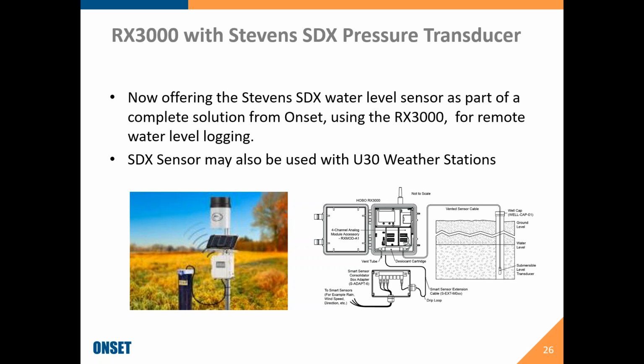The great thing about the RX3000, which is an update to the preceding U30 remote series, is that instead of having to configure an analog module at the beginning of your order and being stuck with it, unable to remove or add another one later, the RX3000 gives you more flexibility. You can install and remove up to two 4-channel analog modules as needed, depending on the type and number of sensors you're using. So it just gives you a lot more flexibility.